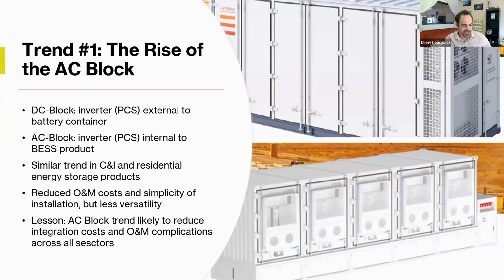So let's go on to the trends we saw out there in the showroom. The first big trend is the rise of what we'd call the AC block. AC block refers to the fact that some battery products are what we call a DC block, meaning the container just has battery racks inside, a collection system where racks are put together in parallel, a cooling system, and fire systems. But the important thing is there's no inverter, so the DC block puts out DC voltage, typically ranging from about 1100 up to just under 1500 volts. So that's a 1500 volt rated system, 1100 fully discharged, up to about 1450 or a little higher fully charged. That's a DC block product.